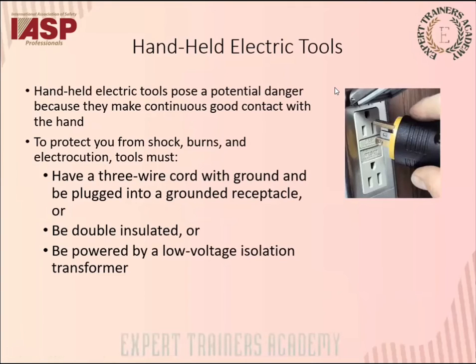Handheld electrical tools. Handheld electric tools pose a potential danger because they make continuous good contact with the hand. So you're carrying portable tools from one place to another to carry out certain work. To protect you from shock, electrical burns, and electrocutions, the tools must have a 3-wire cord with ground and be plugged into a grounded receptacle, or it must be double insulated, double, 2 layers of protection. Either one of the layers will give sufficient protection. That's why it's called double insulation.